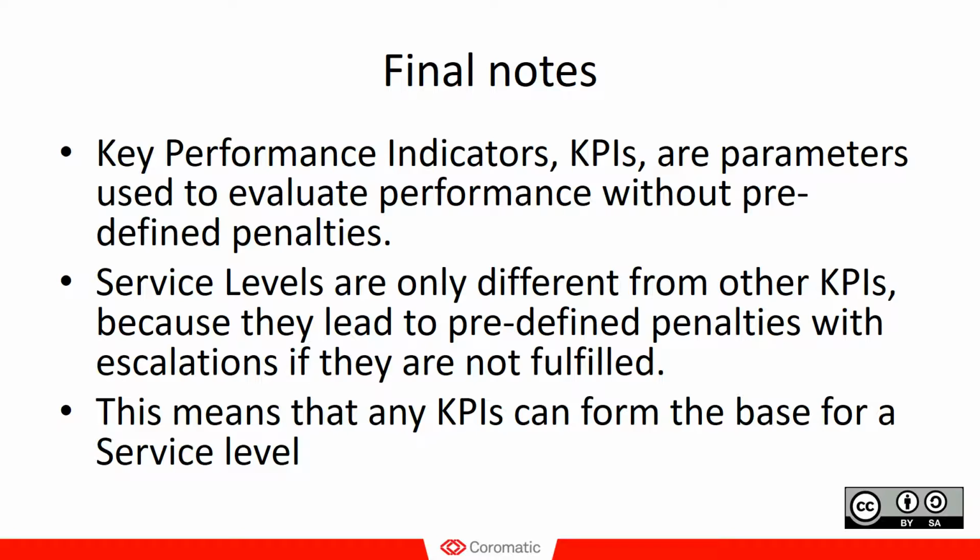For example, you can measure the PUE, power usage effectiveness, of the critical facility. And if you measure it and report it on a regular basis or have it on a live stream in a dashboard, it is a KPI that doesn't reflect on any penalties or anything.